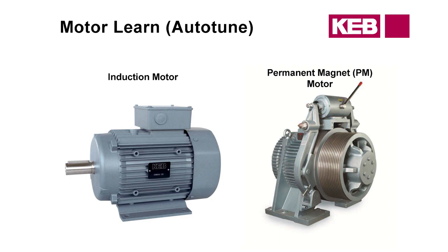We'll start with the motor learn. For induction machines, sometimes this isn't done — that's okay, you don't have to — but we always recommend doing it. It's going to result in better ride quality, lower current draw, and quieter operation, so other than saving yourself a few minutes, we always recommend doing the motor learn for induction machines.